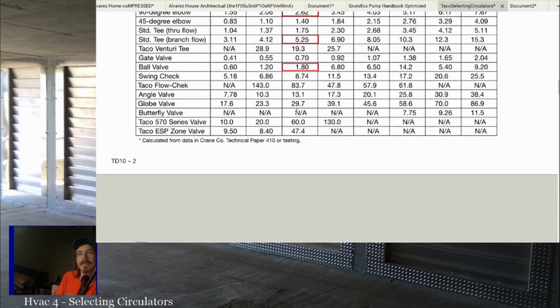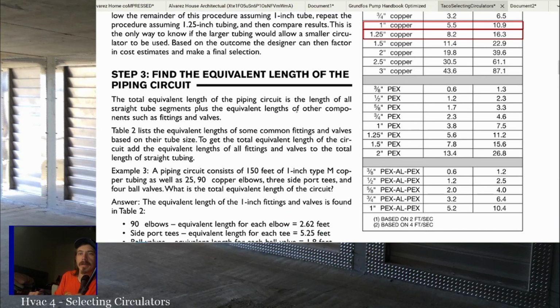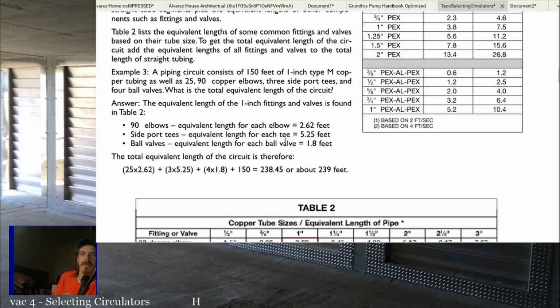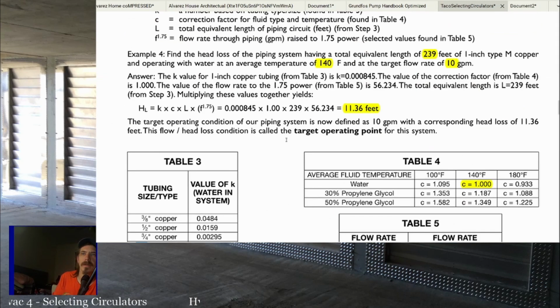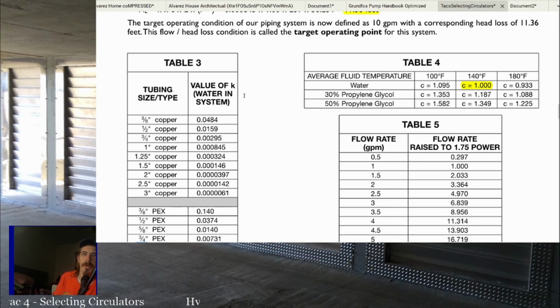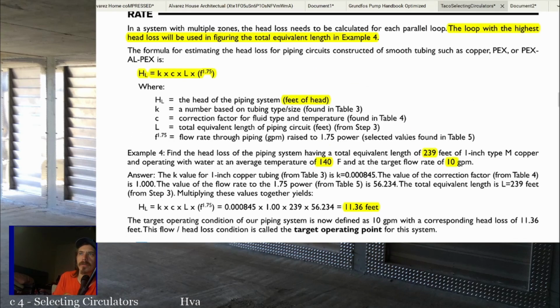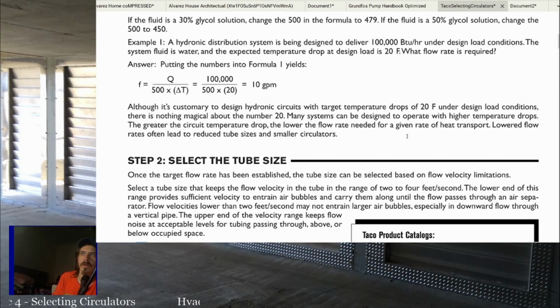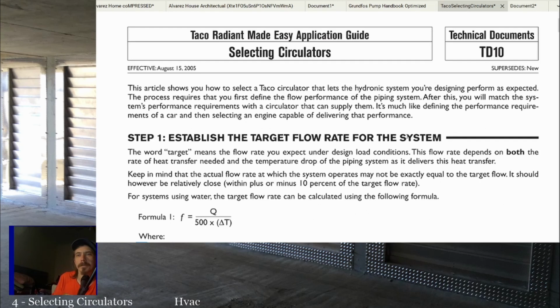So it's pretty easy to do that. You don't even really have to measure some kind of head pressure or anything like that. You can do it if you get the equipment, just like airflow. You can actually measure how many GPM the pump is pumping and do it like that. But a lot of times with boilers, it's just as easy to say, okay, about how many feet of head loss do I have in this system? Based on that, what size circulator do I need, at the GPM that I want, which again is usually just going to be based off a 20-degree delta. And you go from there.